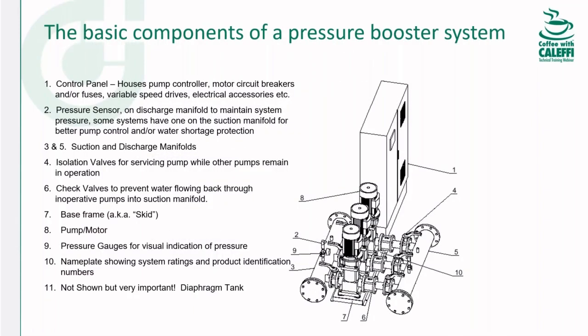Okay, so let's take a look at some of the main components of a pressure boosting system. For time's sake, I'm just going to call out a few items here. The pressure sensor would go on the discharge manifold, and that is our control signal for the process variable. On the suction side, most of the time, like Grundfos will put a pressure transducer on the suction side. Some people do a pressure switch, but at a bare minimum, we need something to monitor for dry run protection, because you don't want those pumps to run dry.